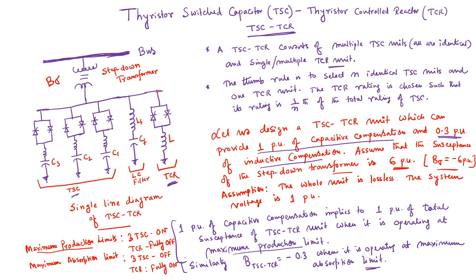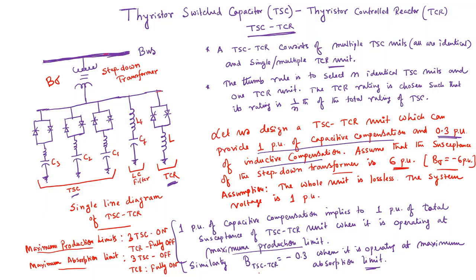This is something one needs to understand very clearly: when the whole unit will be operated at maximum absorption limit, that means we need to turn off all the TSC units and the TCR unit would be fully turned on, then only it can absorb the rated amount of VAR from the system.